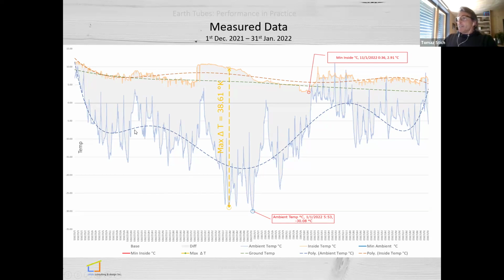So the blue line is the ambient temperature outside. Or sorry, those here. And then this is the basic line, right? So we had minus 30 as the maximum exterior or ambient temperature. And the max delta T was sometime in December 21. So we had 38.6 degrees Kelvin, right? And this is the minimum interior temperature, 2.91 degrees Celsius. This is how it came in. That was the minimum, right?